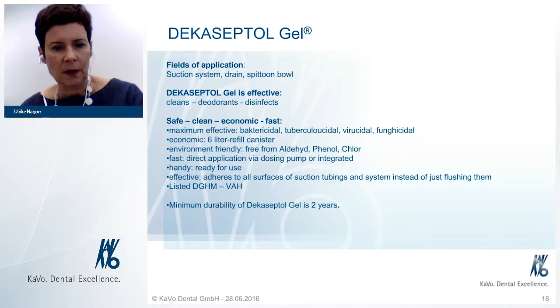So we recommend disinfecting the suction system minimum once per day after the work day, and in some cases it might be even recommended to use it twice per day or after some specific situations. That means in the suction system itself we have again a combination of functionalities in the treatment system that provide the functionality and provide the hygiene maintenance in the suction and drain system.